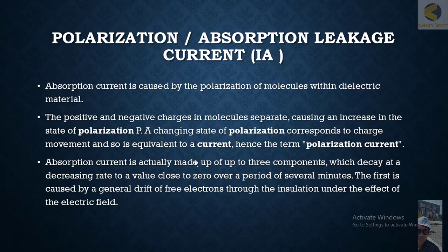Let's discuss the new topic: polarization absorption current. Absorption current is caused by polarization of molecules within a dielectric. A dielectric has molecules, and each molecule has positive and negative charges. When you apply stress on the dielectric, the molecules will try to become polarized, with positive and negative charges aligning near the corresponding voltage terminals. This polarization takes some time to occur.